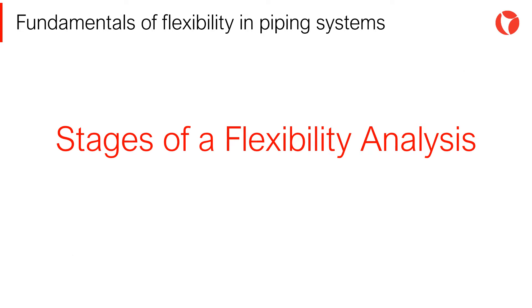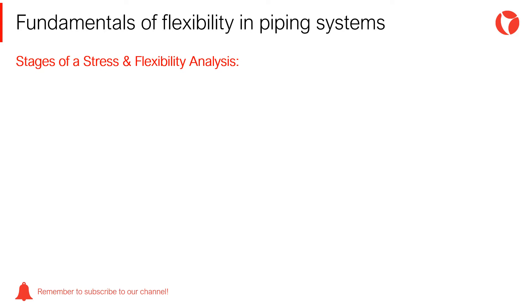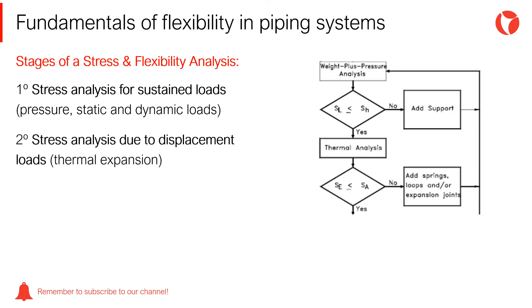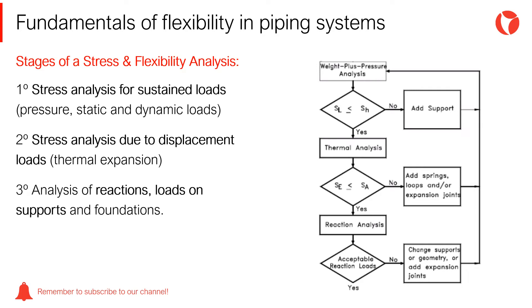The flexibility analysis of a piping system is divided into three stages. First, stress analysis for sustained loads, pressure, static and dynamic loads. Second, stress analysis due to displacement loads and thermal expansion. And third, analysis of reactions and loads onto supports and foundations. All piping systems must meet these conditions.